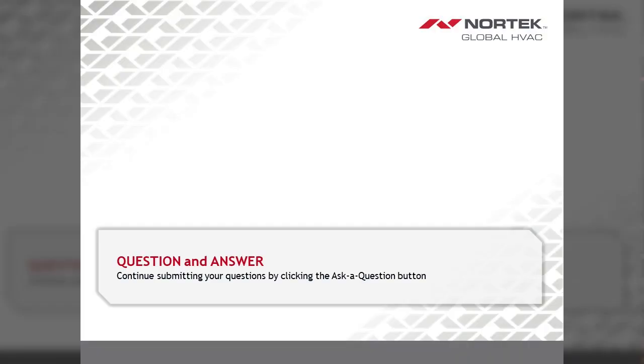The next question is, what's the best way to jump pressure switches for troubleshooting? We talked about it in the video, but essentially all you have to do is wait for the inducer to kick on and then jump the switch out. If you jump the switch out beforehand, you'll get a pressure switch closed fault. On single stage furnaces, it's pretty easy. All you've got to do is take the orange wires off. It'll roll through a call for heat, let the inducer kick on, just wait like 1 second, then jump your orange wires, and that will effectively jump out your pressure switch for troubleshooting.